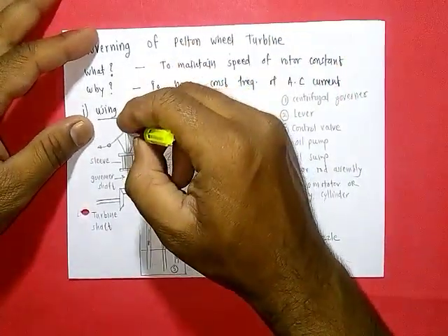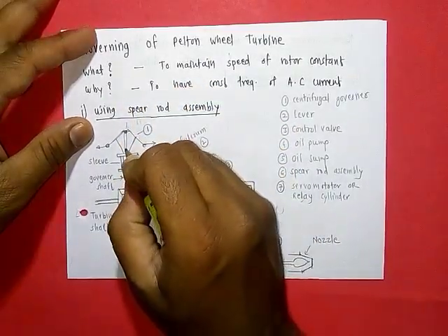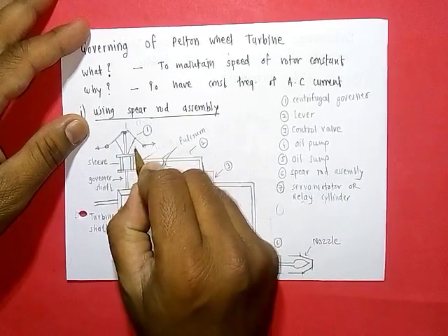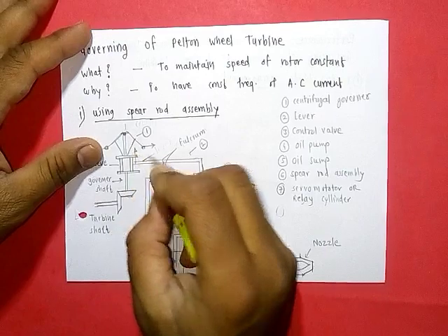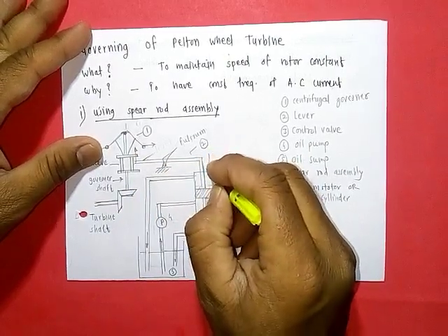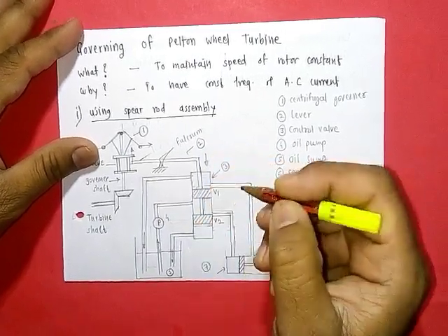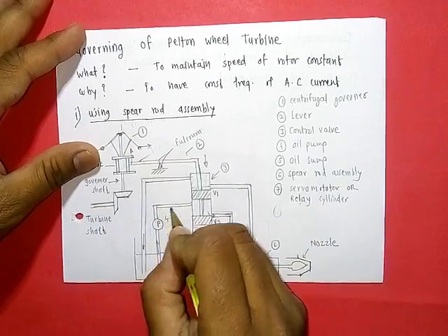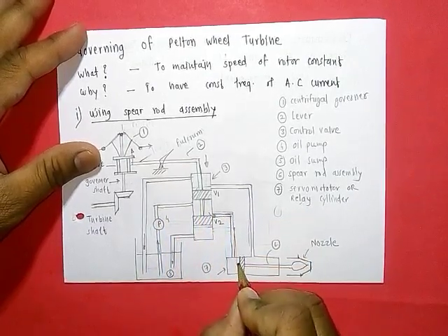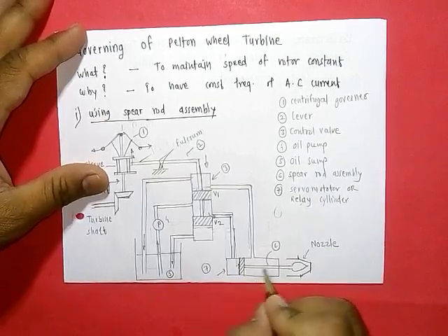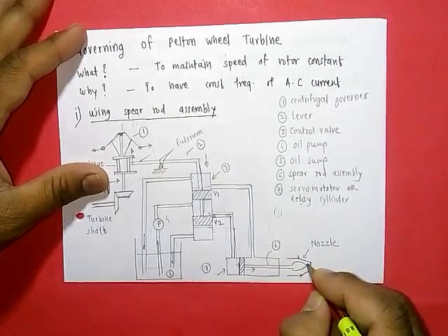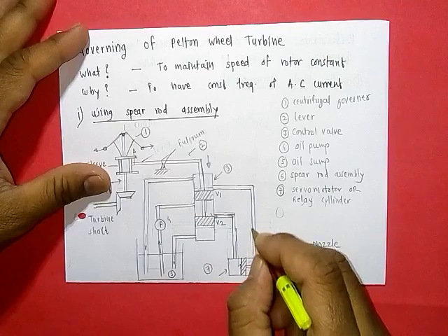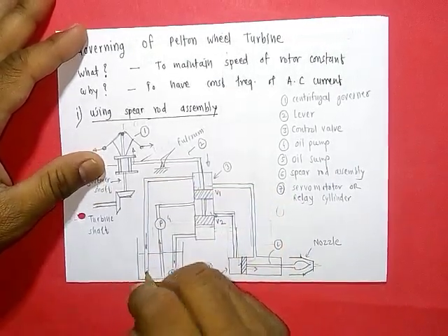As the balls move outward, the sleeve moves upward. When the sleeve moves upward, the lever moves downward, opening valve V2. Oil from the pump flows through valve V2 and pushes the spear rod forward, reducing discharge through the nozzle and hence reducing speed. The return oil passes back to the oil sump.